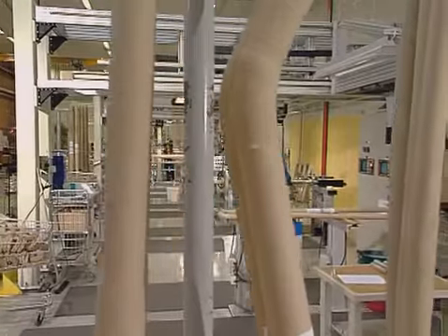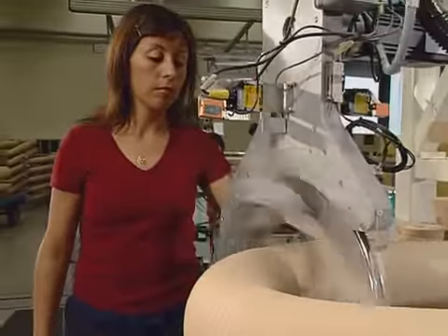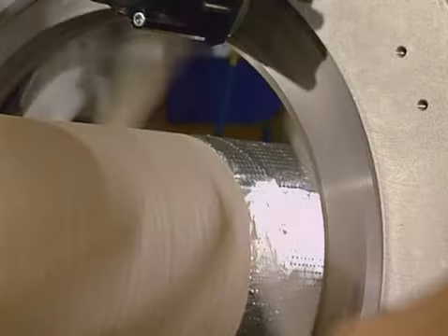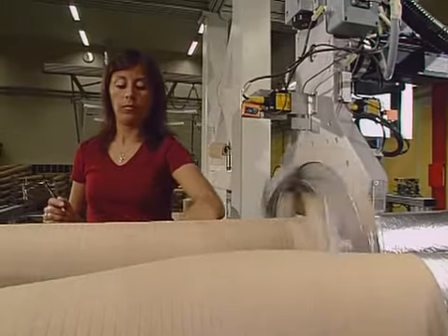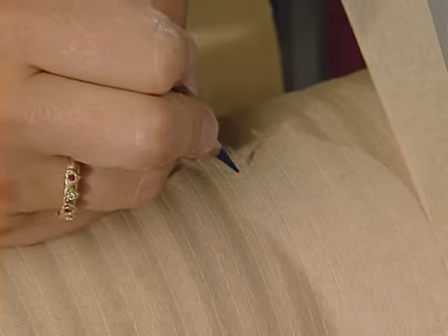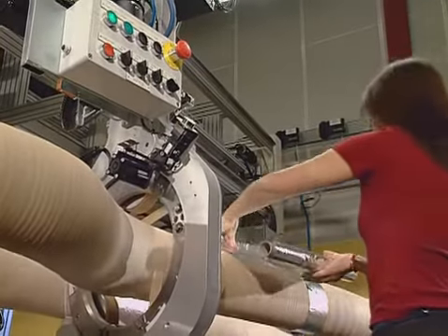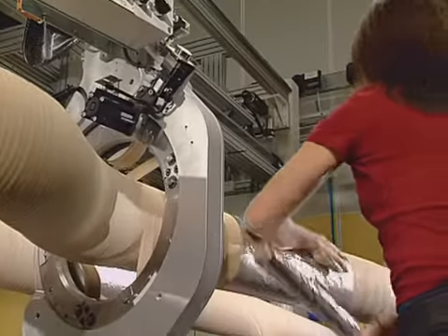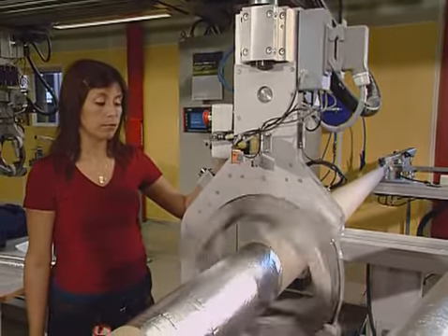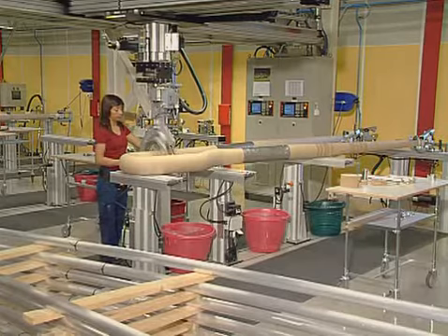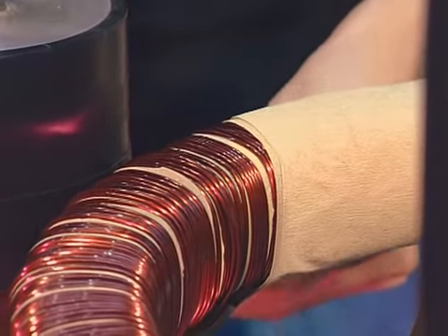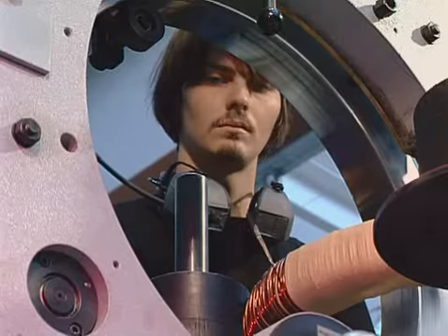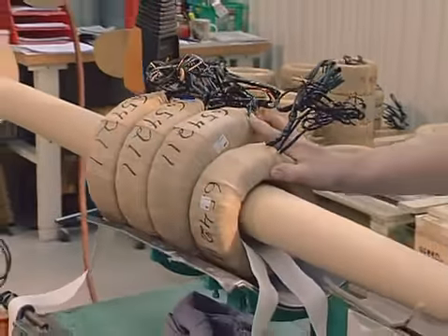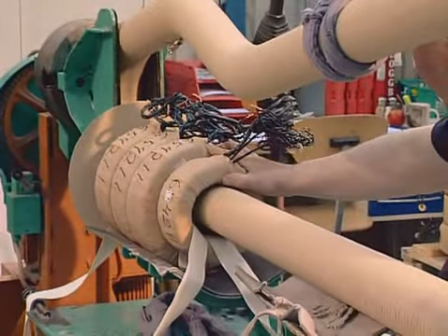ABB's instrument transformers are manufactured in brand new facilities with state-of-the-art automation, which ensures consistent high quality. The primary winding of the current transformer is insulated with paper. In order to achieve an even voltage distribution in the insulation, the winding is provided with capacitive layers. The secondary winding is built on a core, where the size is determined by the customer's specification. The completed cores with a secondary winding are mounted on the primary winding.